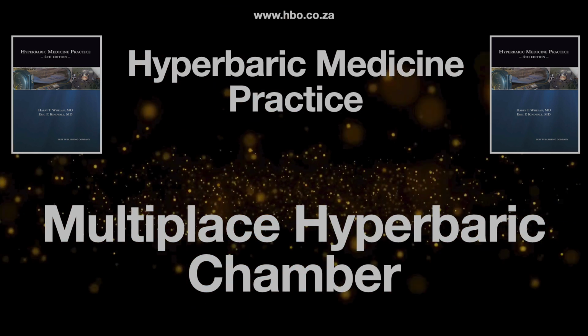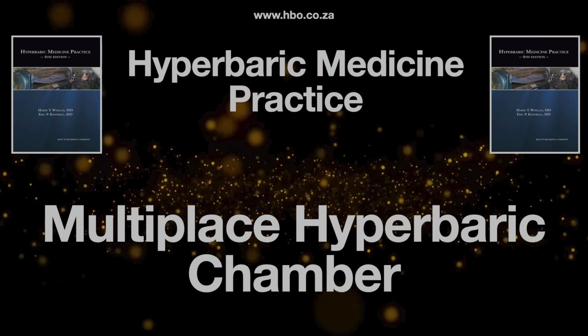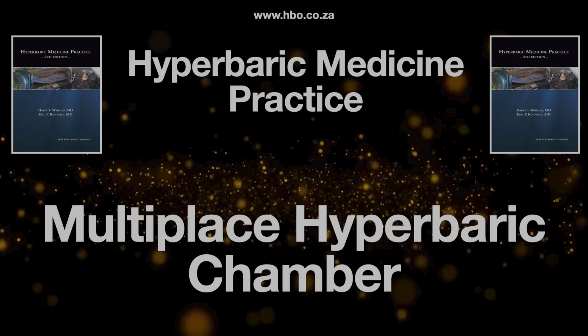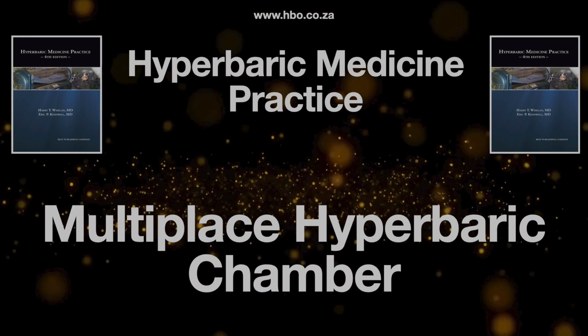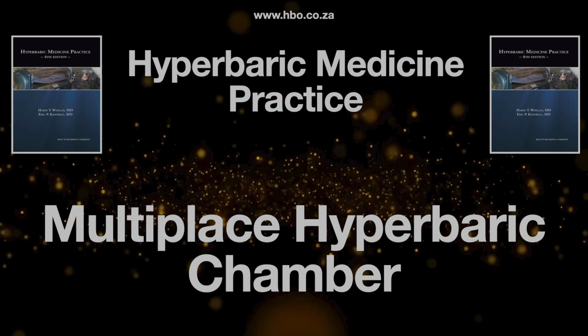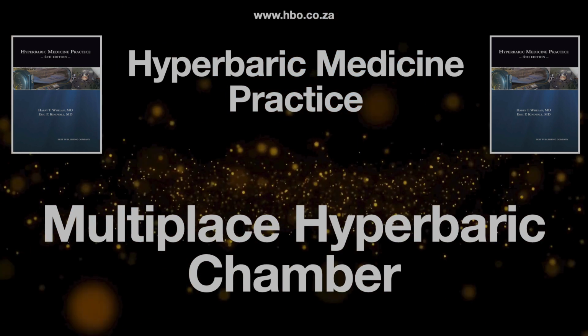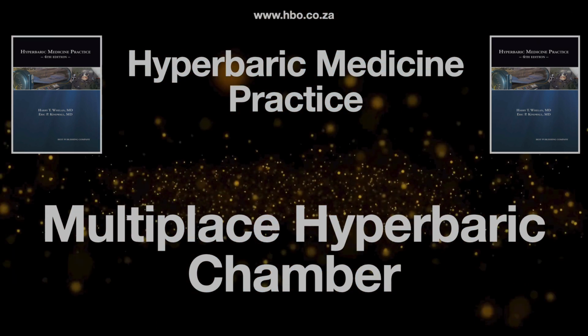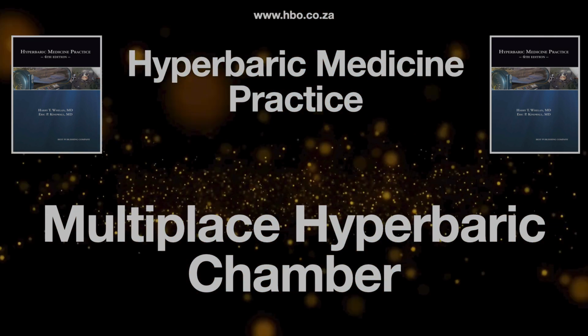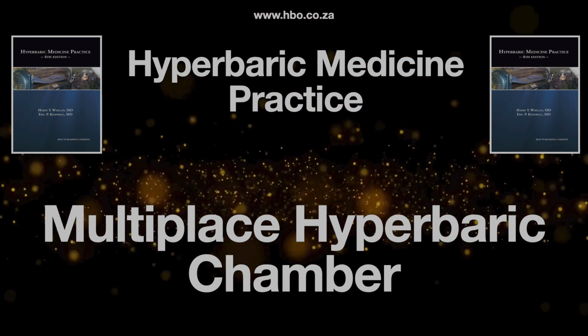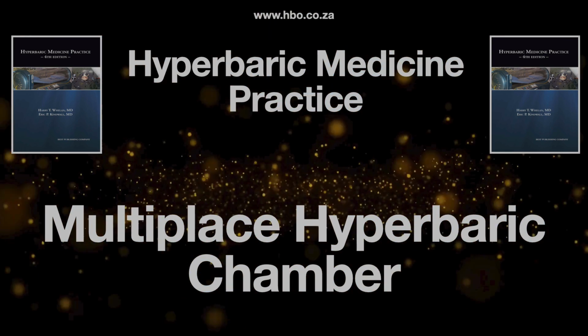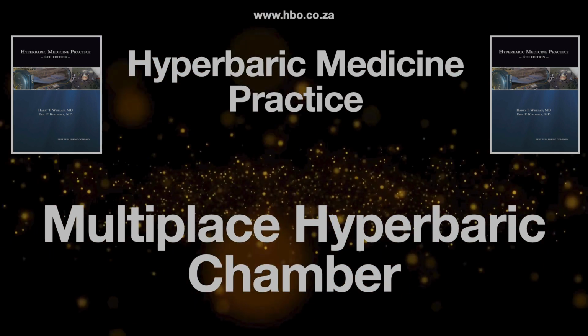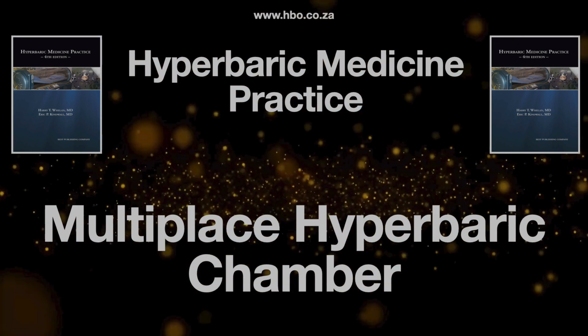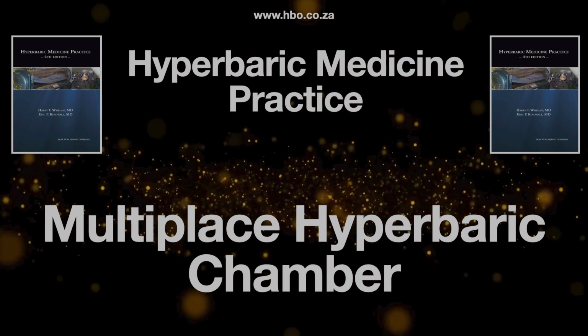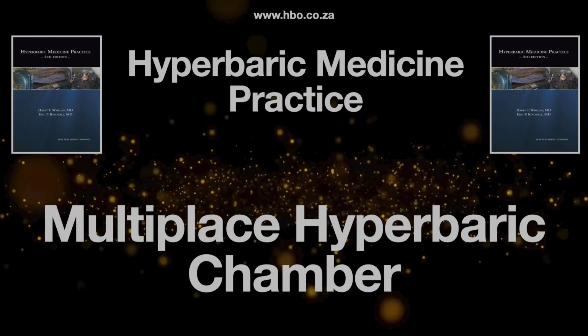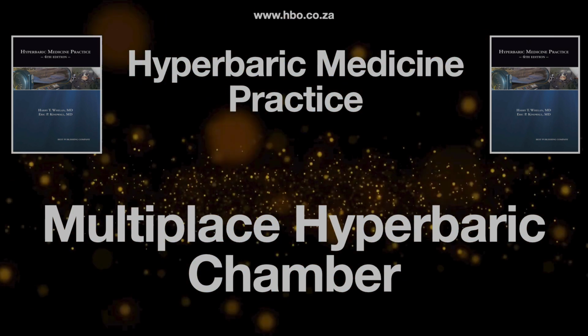Right. There are basically two types. Constant volume ventilators try to deliver a set volume of air with each breath. But as density goes up, the flow rate might drop, reducing the actual volume delivered. So these often need manual tweaking as the pressure changes. Okay. Then there are pressure-controlled ventilators. They aim to maintain a constant pressure during inhalation. The flow might still be affected initially by density, but many modern ones have smart algorithms. They detect flow changes and adjust the pressure automatically to keep the tidal volume stable. Much more sophisticated. Definitely. Better for adapting to the changing conditions inside the chamber.